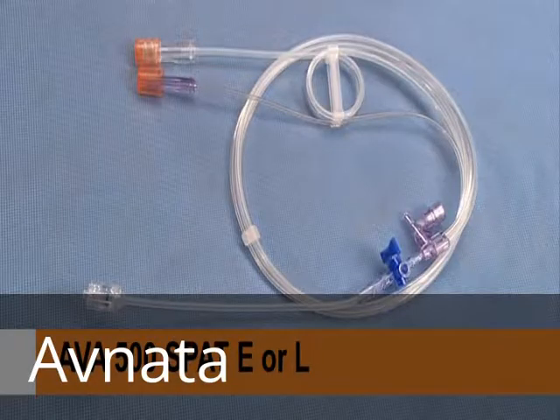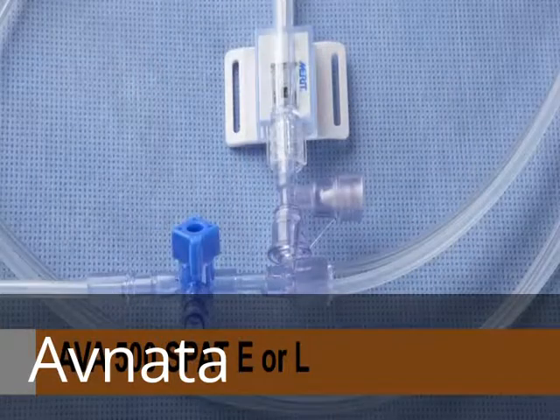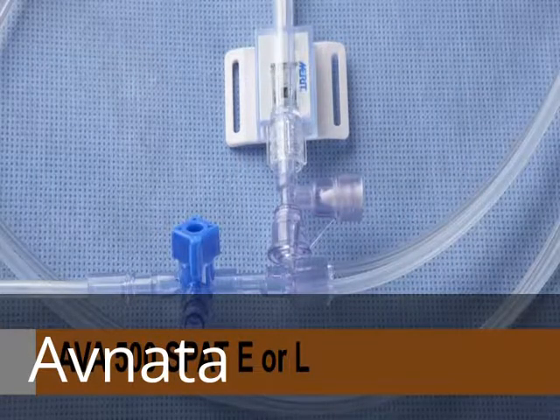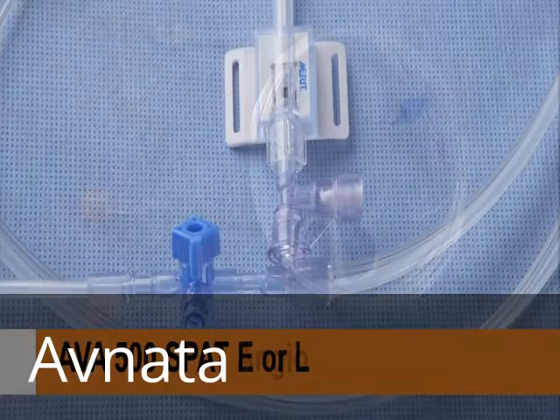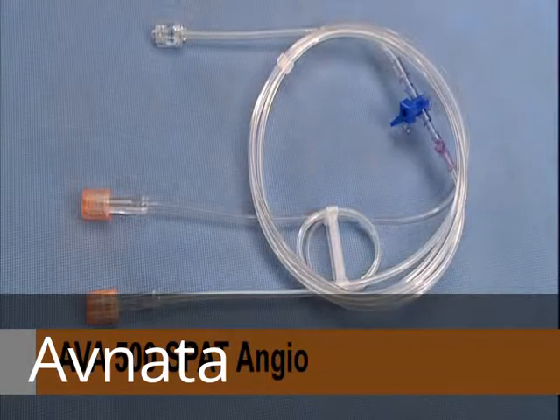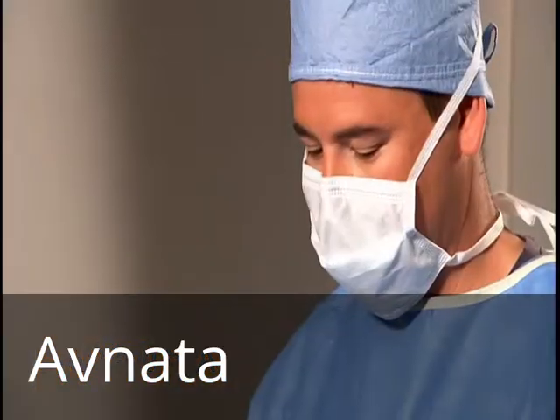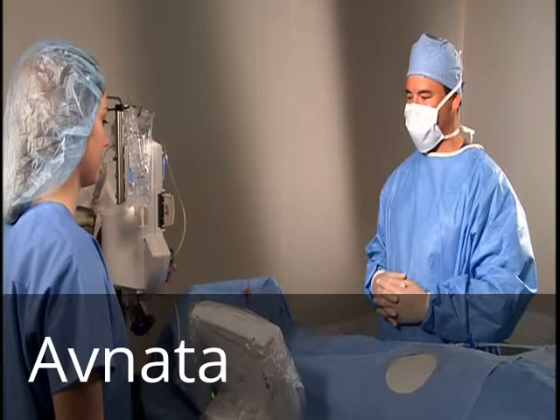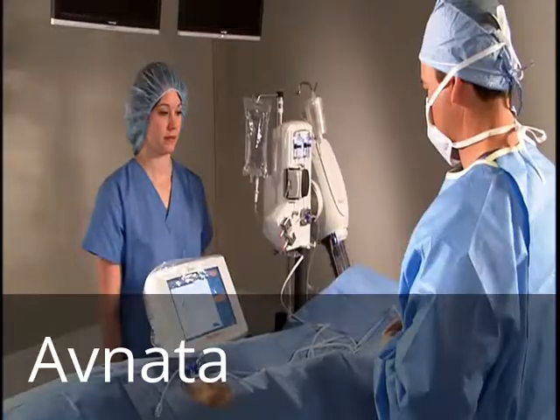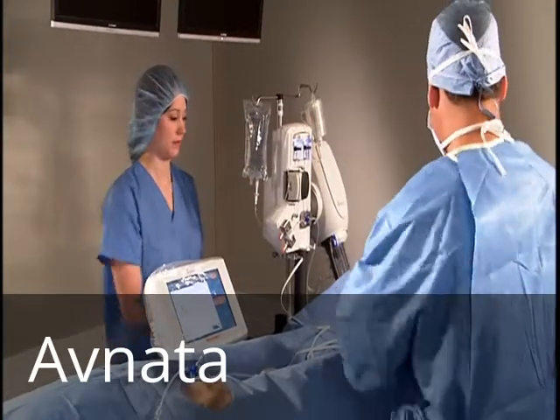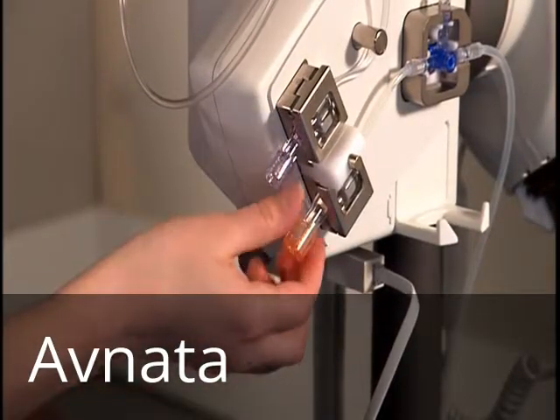The purge process of single-patient disposables AVA500 SPAT-E and AVA500 SPAT-L, which are intended for use with an attachable pressure transducer, differs from the setup of AVA500 SPAT-Angio, which is used without a pressure transducer. To connect any of the SPAT versions to the MPAT, perform the following steps. Remove and discard dust caps from MPAT and SPAT.